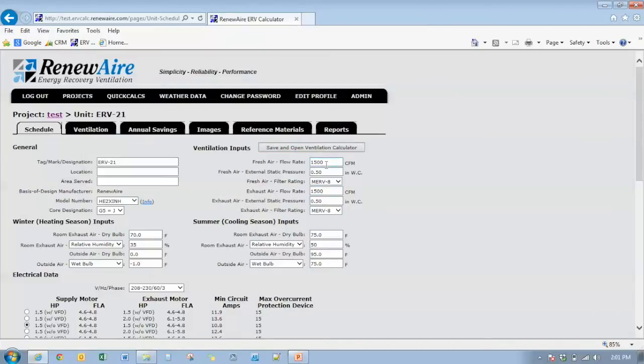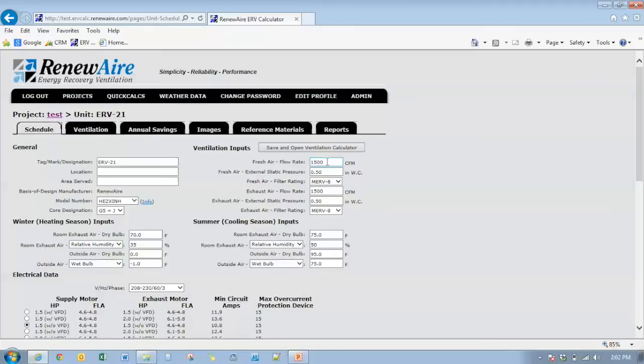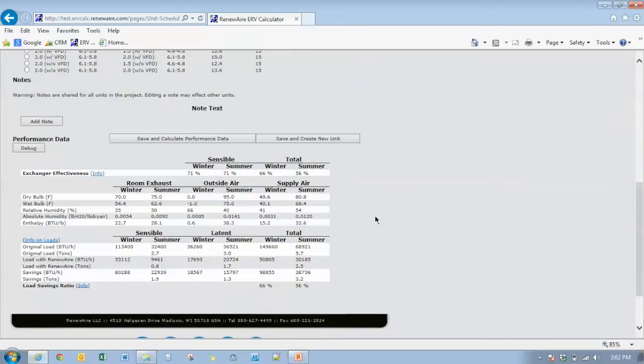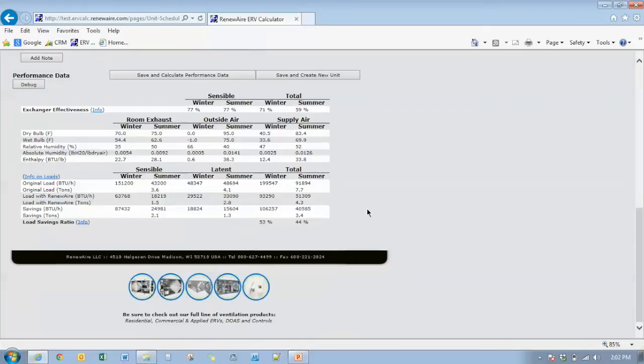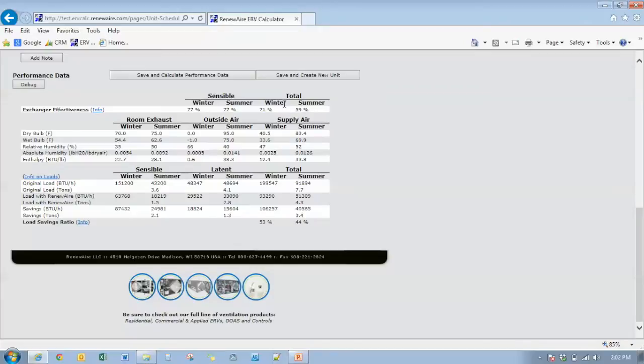If we unbalance the airstreams, let's say we go to 2000 CFM of fresh air and 1500 CFM of exhaust air and go down and calculate performance data. Now you can see those effectiveness numbers have changed fairly significantly. The exchanger effectiveness has gone up because the ability of the core to transfer energy has increased primarily in the exhaust air stream.